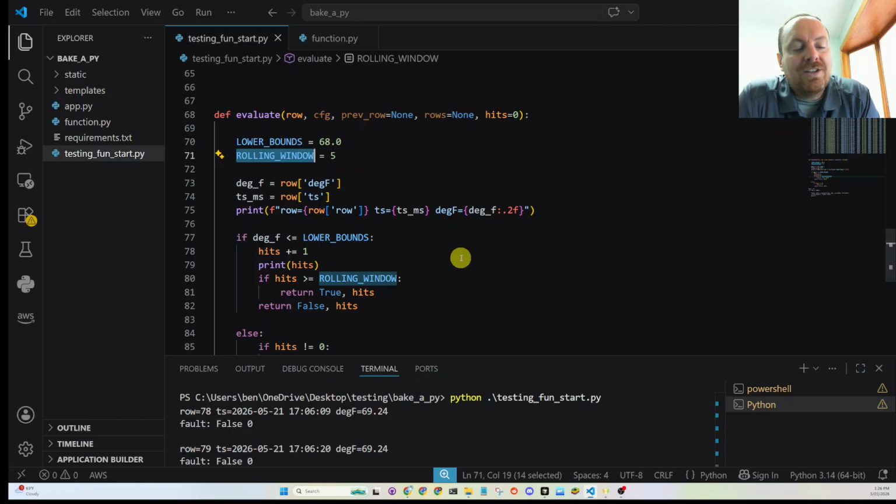If this was a sensor on the chilled water system where the chiller is doing lots of work, all of a sudden the sensor could drop 5 degrees in 30 seconds, so it would have to be appropriate for the type. If the chiller's running, what range should this be reading, and then the same with a zone temperature sensor.